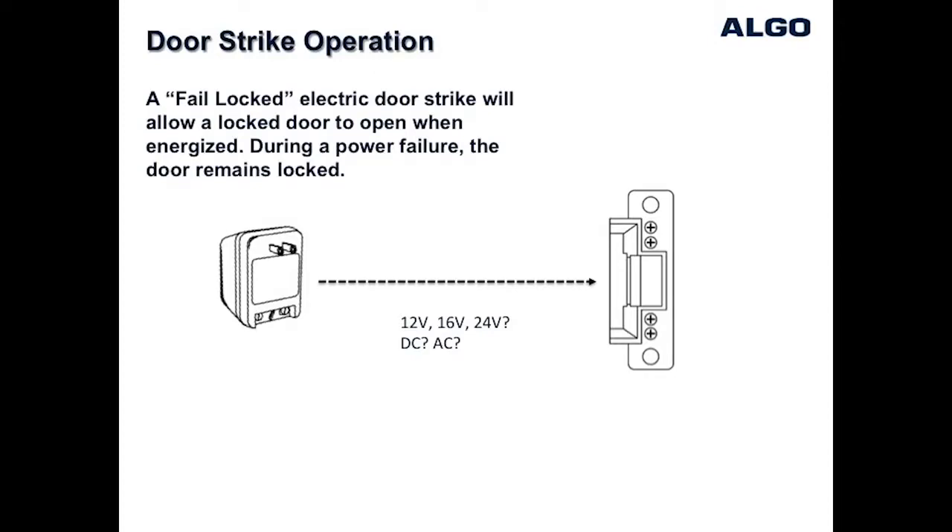There are many types of door strikes depending on the type of door jamb, and many operate at different voltages such as 12, 16, or 24 volts DC or AC. It's important to know which voltage your door strike requires and also to have a power supply that matches the door strike voltage.